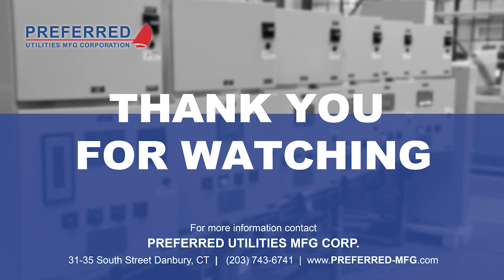Last question, unless somebody pops a new one in. Is using a temperature sensor in day tanks to cycle cooler fuel necessary in the Northeast? I would say not. I'm based in Dallas, where it gets ungodly hot for about 5 months of the year. It seems like we had 60 days last summer of 105 degrees, and we don't do what you're talking about in all of our fuel systems here in Dallas, and nobody I'm aware of had issues with hot fuel.